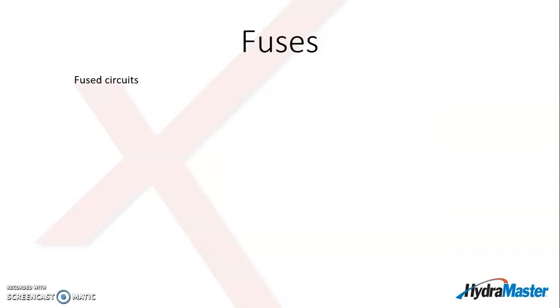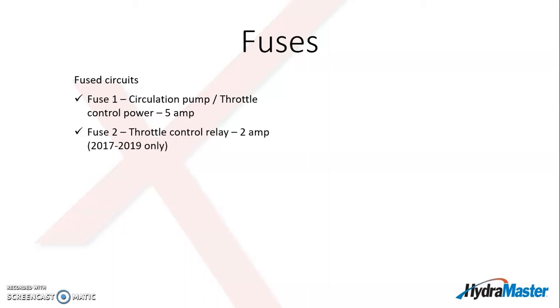So some of the fused circuits, we'll talk about what those fuses are. Fuse 1 is the circulation pump. That's the pump that pumps the water through the motor and the generator and through the heat exchanger. It's also the power for the throttle control. And that's a 5-amp fuse. So fuse number 1, 5 amps.